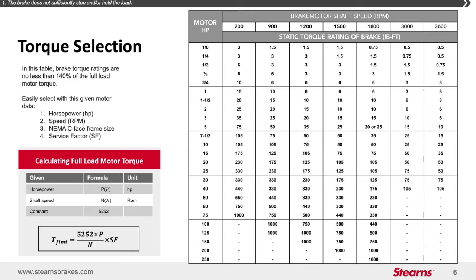At Stearns, we typically use a service factor of 1.4, meaning that our recommendation is that the torque rating of the brake be 140% of full load motor torque for NEMA B class motors. An electric motor brake is typically rated at 140% of full load motor torque, so the motor is not able to simply drive through the brake if the brake is not properly released. If the motor is held by the brake without rotation, the motor will demand locked rotor current, which will tend to make the motor thermal overload protection disconnect the motor and the brake from power in a timely manner, so to protect the motor and brake.